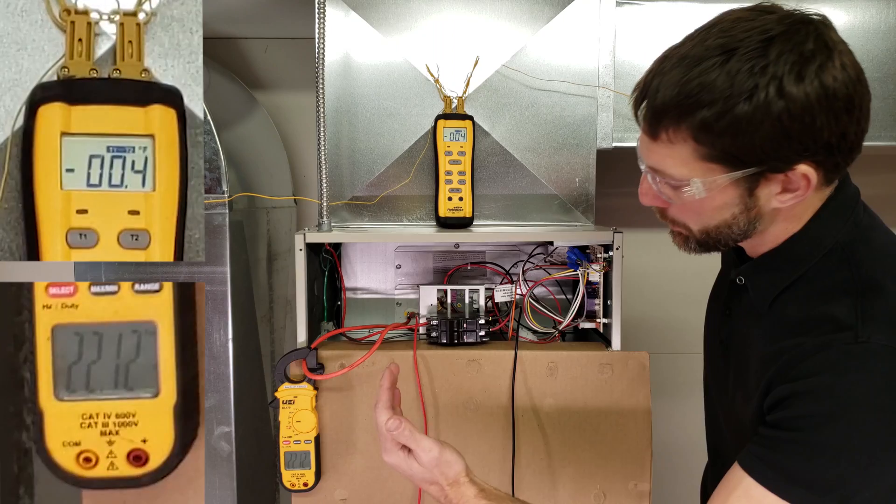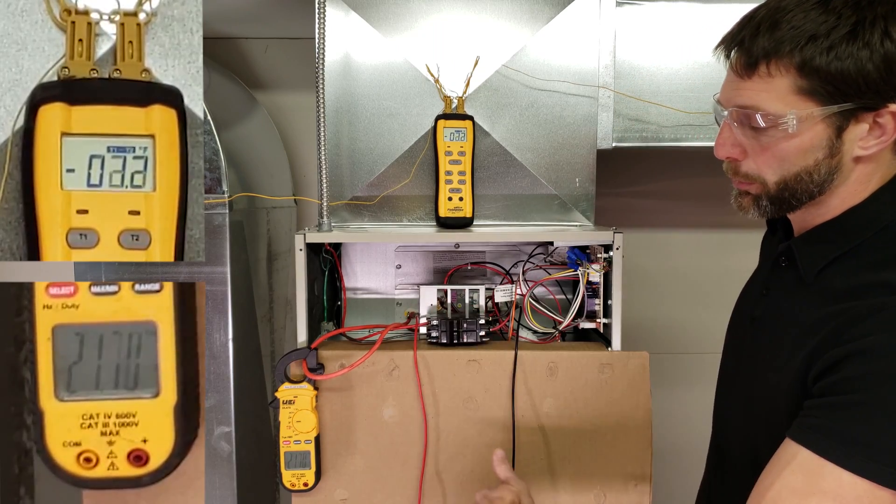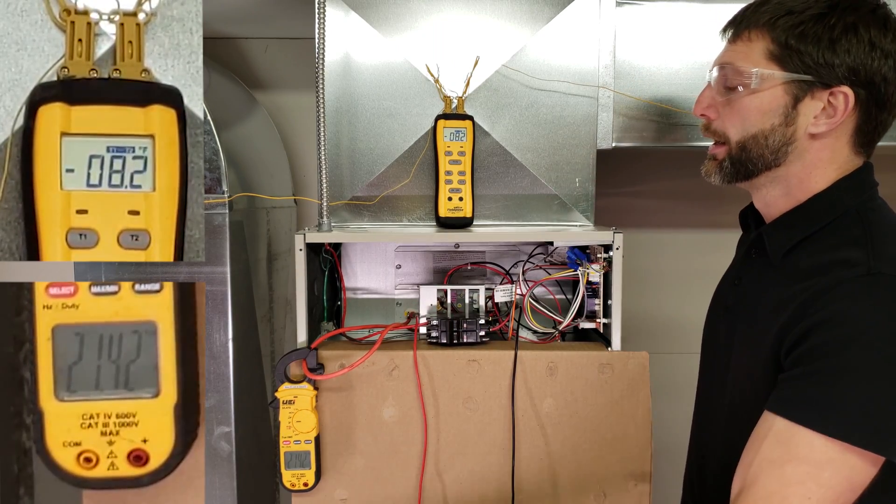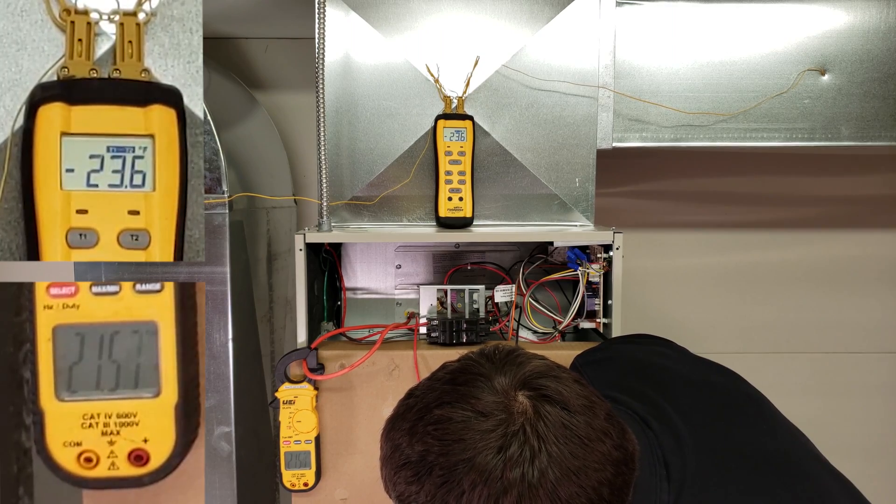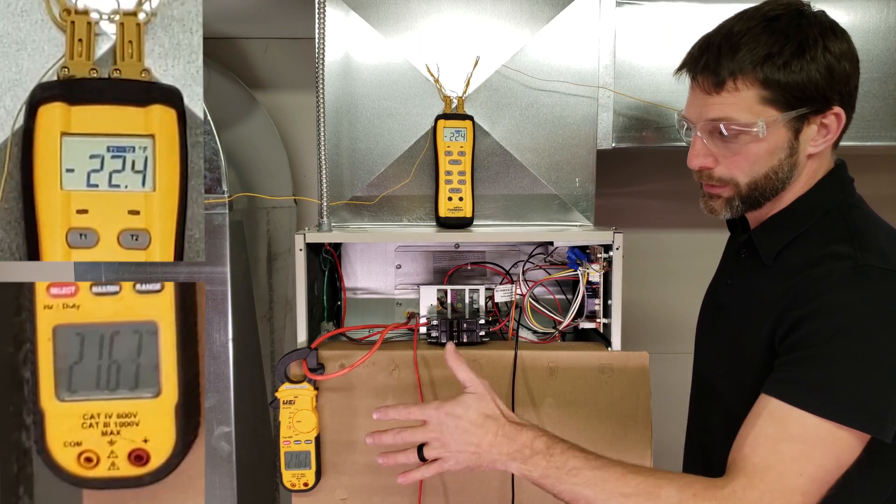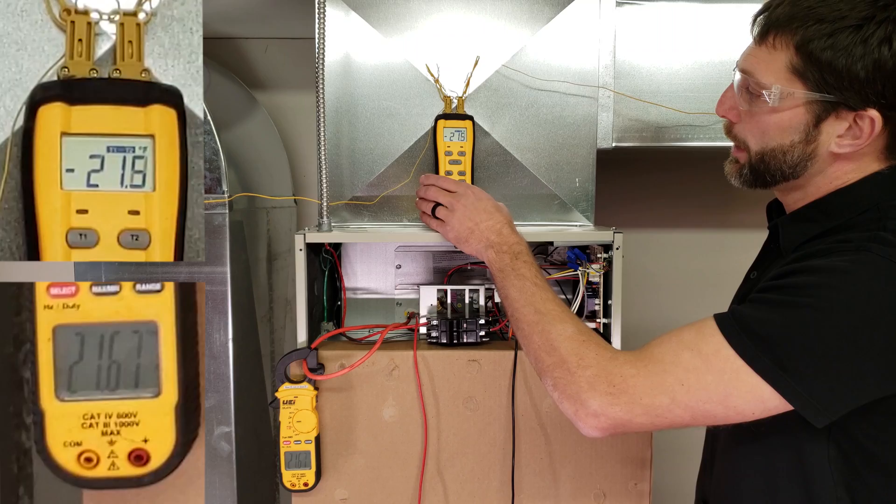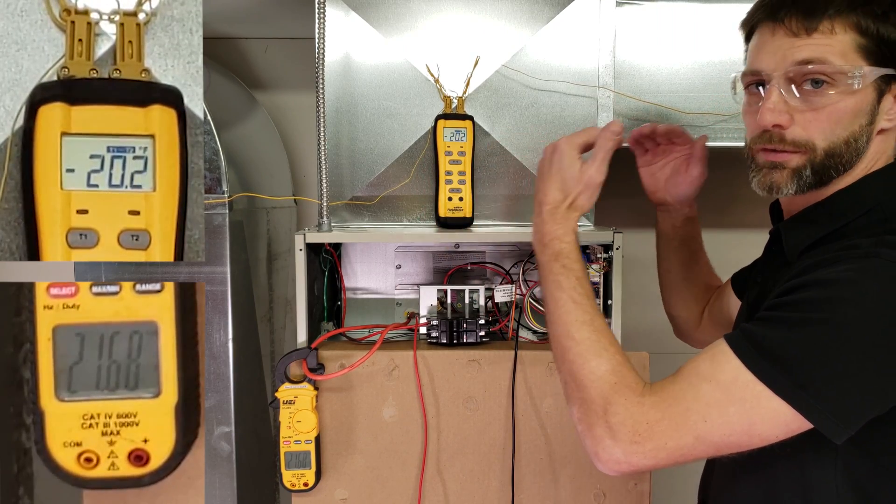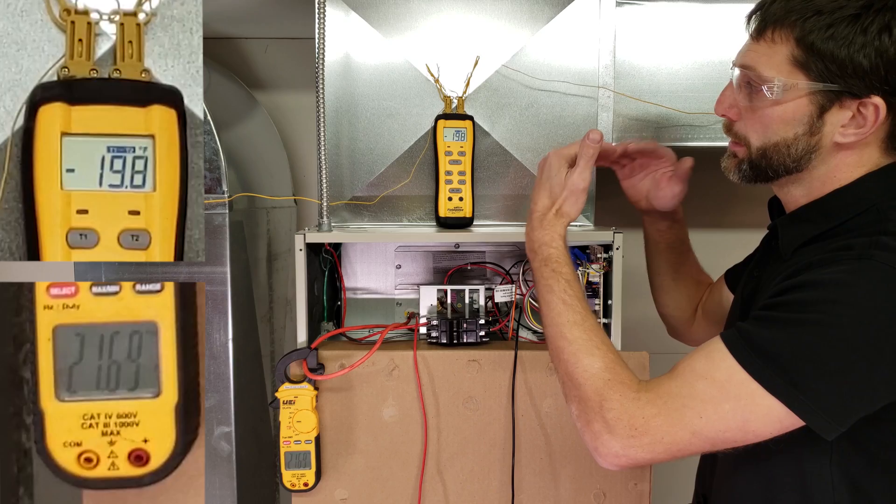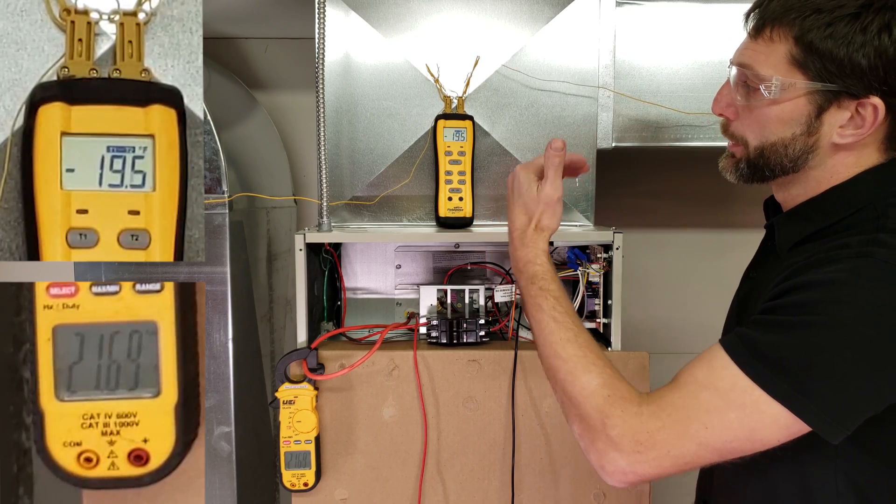So first thing, the electric resistance is getting powered, and then the blower motor is going to turn on. And let's check our amperage looks to be right about 21.6 amps. And our temperature differential, what we're looking for is that we're looking for it to settle in into a constant temperature differential.